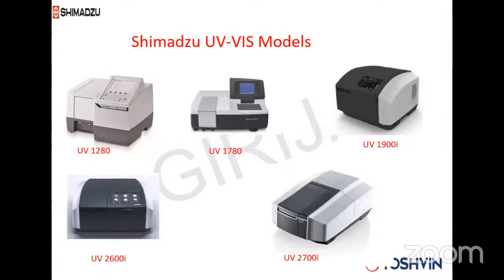And finally, these are the different models from Shimadzu. These are the UV visible models. I told you UV 1280 is purely for water analysis. We are not promoting it anywhere else. It is a 5 nanometer single beam equipment. Only 1280 is a single beam equipment. Rest all equipments are double beam equipments.